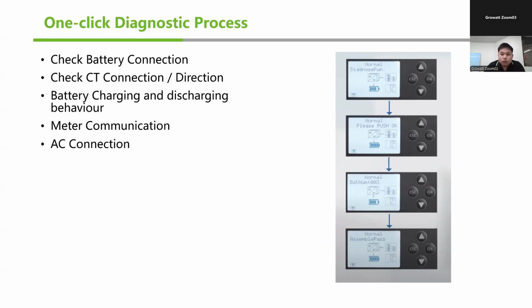So it's going to do 5 kinds of checks. It's going to check the battery connections. Are these batteries connected with each other, connected with the inverter? And it's going to check the CT connection. Is the CT reading the required data from the grid? Is the direction from the CT correct? And the third thing is, is the battery discharging and charging normally? Is there any issue with the battery charging? And the fourth thing is the meter communication. Is the meter working? Is the meter reading the required values? And the last thing is the AC connection from the grid. Is there any issue coming from the AC connections, or is everything fine?